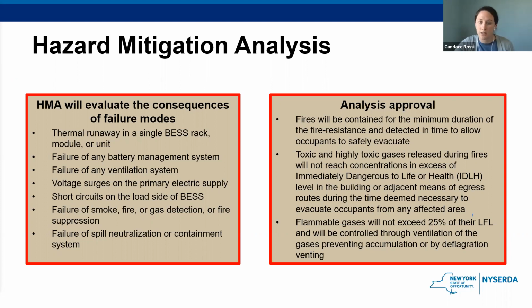So thermal runaway in a single energy storage rack, module, or unit, failure of any battery management system, failure of any ventilation system, if there's a voltage surge on the primary electric supply, if there's a short circuit on the load side of the storage system, what happens if there's a failure of smoke, fire, off gas detection or suppression, and a failure of the spill neutralization or containment system, which we will get into those specific requirements and systems as we continue through this. But really, this hazard mitigation analysis is doing that test to see what will happen if any of these failures happen.